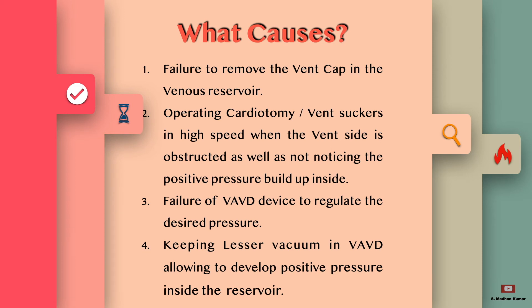What can cause this over-pressurization? A failure to remove the vent cap in the venous reservoir, or obstructing the vent side of the venous reservoir. Operating cardiotomies or vents at higher speed when the vent side is obstructed, as well as not noticing the positive pressure built up inside the venous reservoir.